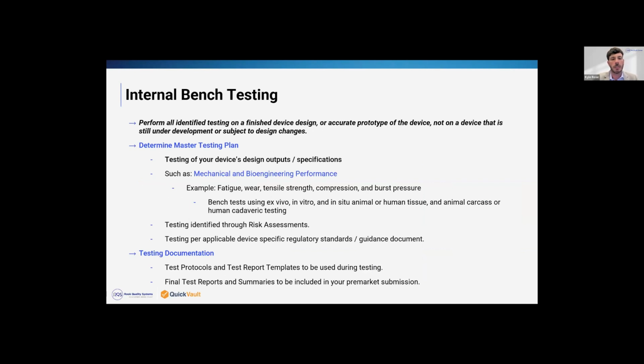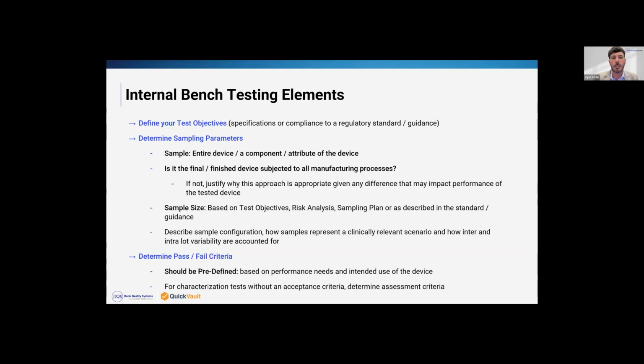Also want to touch a little bit on the internal bench testing. The external standards we talked about, biocompatibility, 60601, cover high level. A lot of times your device is specific to what you do exactly, so there are tests that aren't captured with standards. So you will need to do some internal bench testing to make sure you've captured all the features of your product. This includes what we talked about earlier: writing protocols, determining your sampling justification, your sample size based on risk, and then determining your pass-fail criteria for this. All this should be formally documented and approved prior to starting internal bench testing.